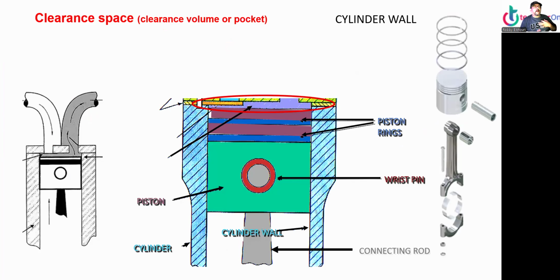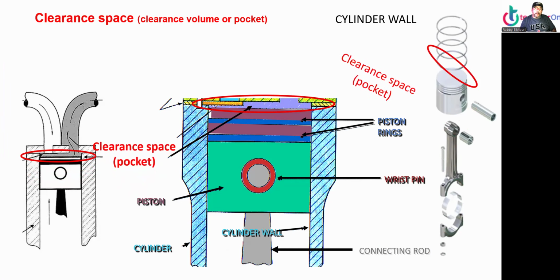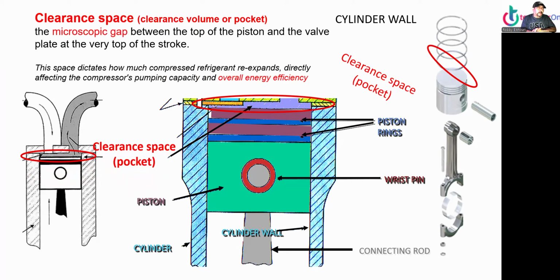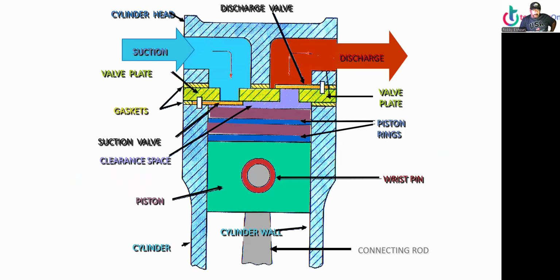Right. Let's move on. Now let's talk about the clearance space, clearance volume, or clearance pocket. Everybody calls it different. It's all clearance though. It's that little tiny space between the pistons and the valve plate. That little tiny clearance is the microscopic gap between the top of the piston and the valve plate at the very top of the stroke. The space dictates how much compressed refrigerant we can have and the capacity and overall energy efficiency.